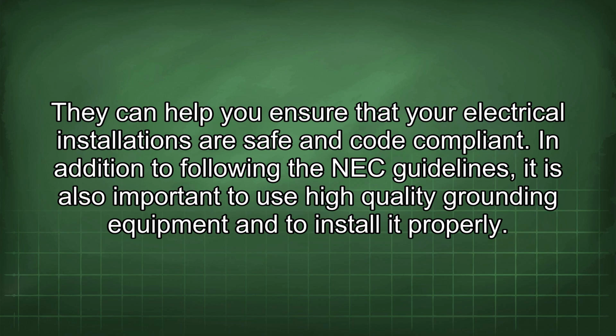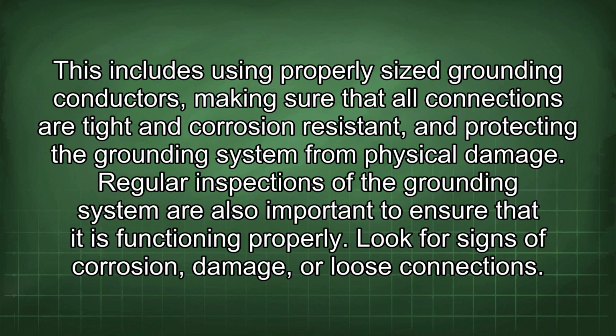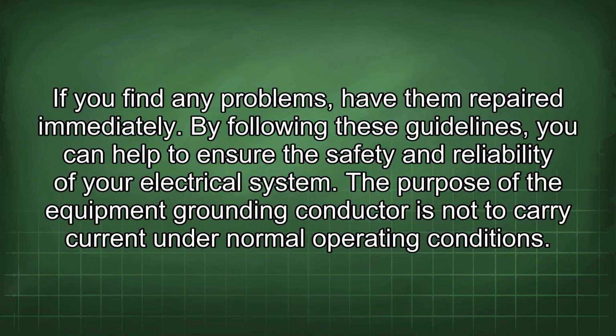In addition to following the NEC guidelines, it is also important to use high-quality grounding equipment and to install it properly. This includes using properly sized grounding conductors, making sure that all connections are tight and corrosion resistant, and protecting the grounding system from physical damage. Regular inspections of the grounding system are also important to ensure that it is functioning properly. Look for signs of corrosion, damage, or loose connections. If you find any problems, have them repaired immediately. By following these guidelines, you can help to ensure the safety and reliability of your electrical system.